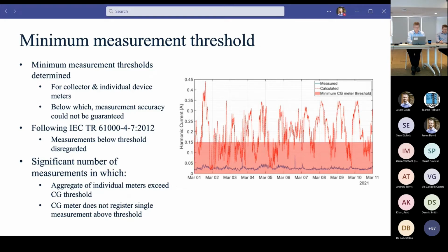So just noting there that there were a significant number of measurements. When I say significant number, I mean the vast majority of measurements were actually invalid or fell below the minimum measurement threshold across all harmonic orders for the collector group. And there are a lot of harmonic orders that do not register a single measurement above this measurement threshold. So entire harmonic orders were dismissed just in this process.